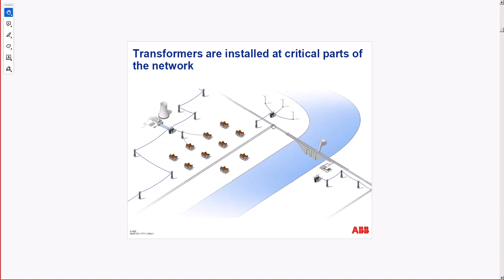Those are part of the transmission substations usually. And then we have the step down transformers again to the distribution, like we have the distribution 44 kV and 27 kV in Ontario. Those are the medium voltage, and further down to the building, so 600 volt and whatever the end user needs, 3-phase 208 for your house and so on. So those are the transformers that are everywhere.